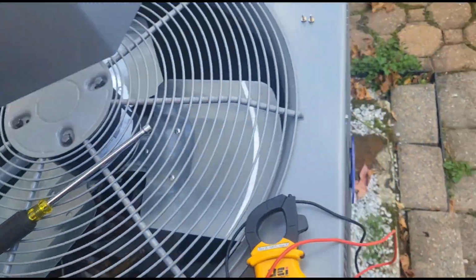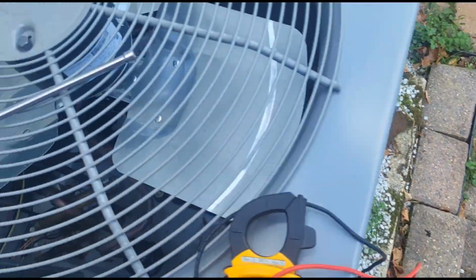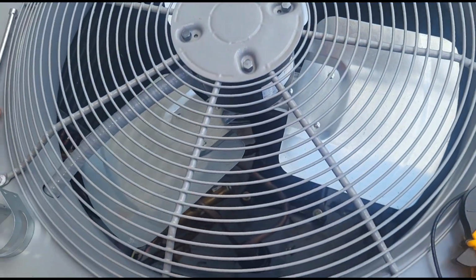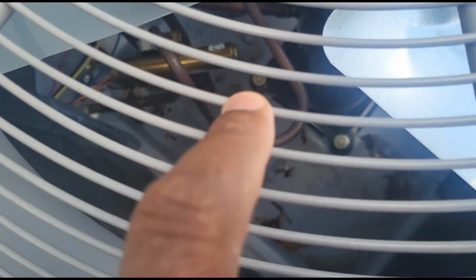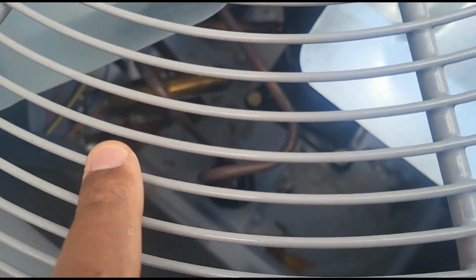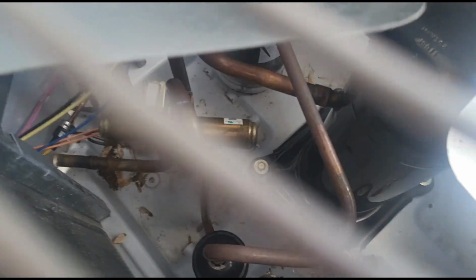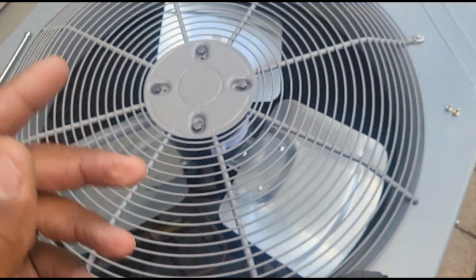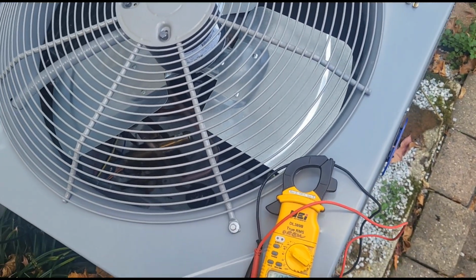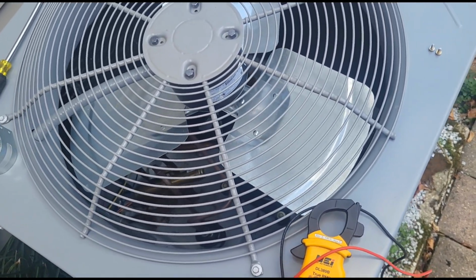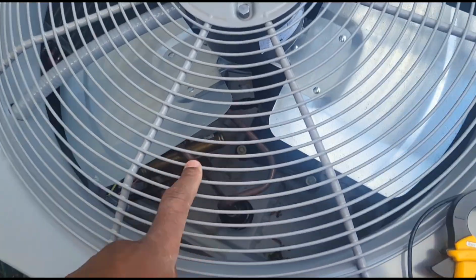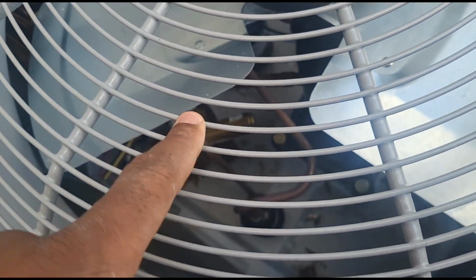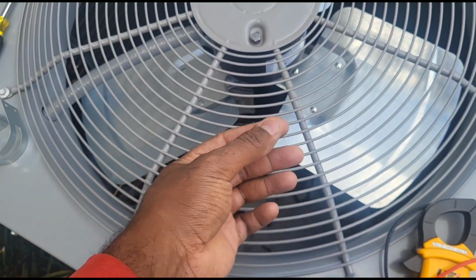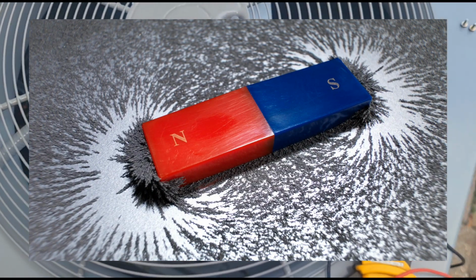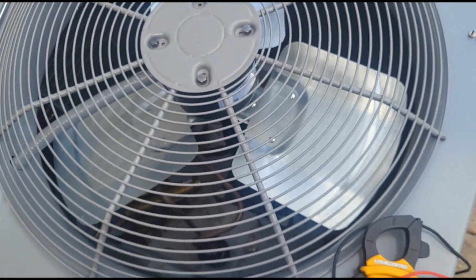But guys, another thing I want to go over - I saw this in a forum maybe 5-6 years ago. One thing I never got the chance to try before, and you guys see this here, this is my four-way valve, or my reversing valve. I've only seen one stuck reversing valve in my brief 11-year, going on 12-year HVAC career. One thing I saw on the forum, there was a service tech that had a no-heat call on a Carrier heat pump, similar to this one. What the tech said was he used a magnet to unstick the four-way valve.